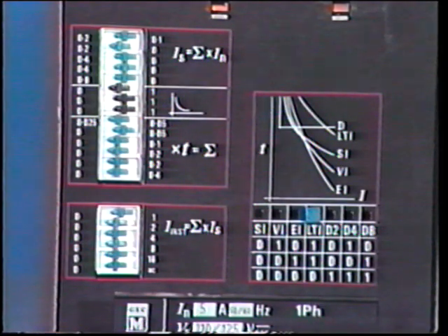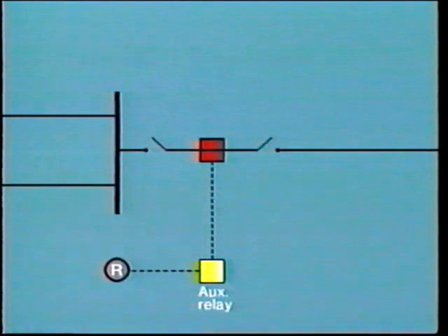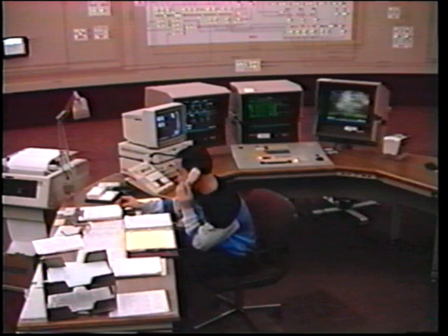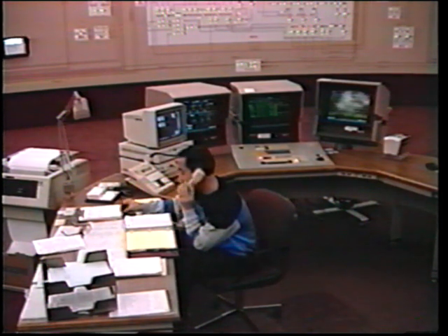Usually, a sufficient number of calibration points are checked so as to verify the characteristics of the relay. For example, the time over current characteristic of an overcurrent relay. As soon as the calibration tests are completed, operational tests should be performed to make sure that the desired breakers actually trip for relay operation. The breakers would, of course, be isolated from the power system by disconnects. But even so, this operation should be coordinated with the system operator.